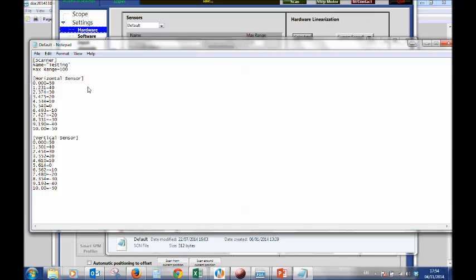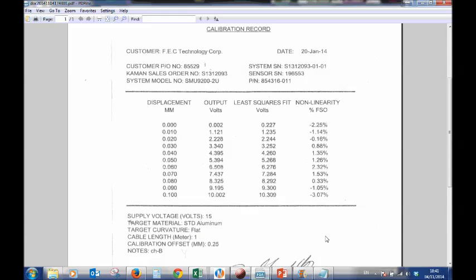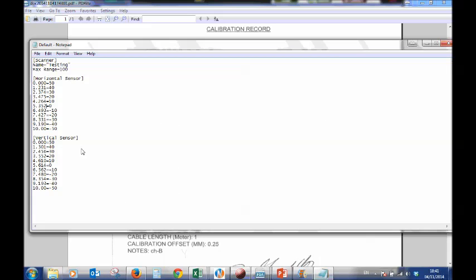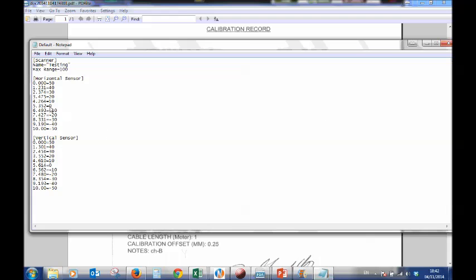You can open it with a notepad, and you see here the calibration. How do we calibrate this file here? So we have to remember that our range is from 0 to 100 microns, and we want to make sure that the center is going to be the 0 position of the scanner. That means that 50 microns will be the 0 position of the scanner, because the scanner will move from 0 to minus 50 and plus 50 microns. So therefore, here we have to make sure that the 0 is the 50 here. That means it should have a value of 5.394.